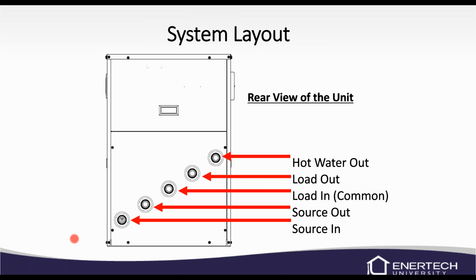So you've got the hot water out on the top, and then it kind of goes down from there, load out. You've got a common load in for your home and for your domestic hot water, and then your source out and your source in. On the source in, you're going to have a strainer on there, so make sure that you pipe that in. The strainers come with the unit. Whenever we have a braze plate, we have to protect them with a Y strainer, and that's a requirement from the braze plate manufacturers. So we'll use a strainer here as well.